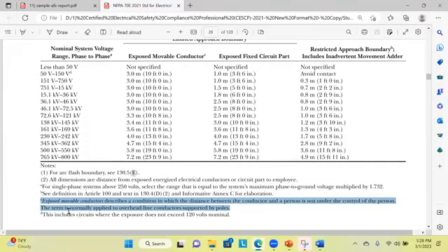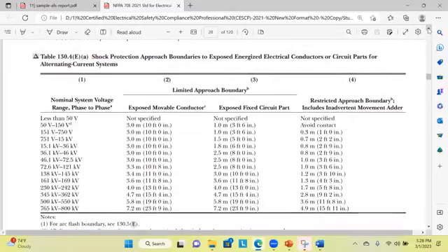So here you can see that exposed movable conductor describes a condition in which the distance between the conductor and a person is not under the control of the person. The term is normally applied to overhead line conductors supported by poles. That distance can be reduced if there is heavy wind, due to the sag. The conductors can move a bit right or left, so this distance will be reduced. If this is the type of condition, we will be using column number 2.